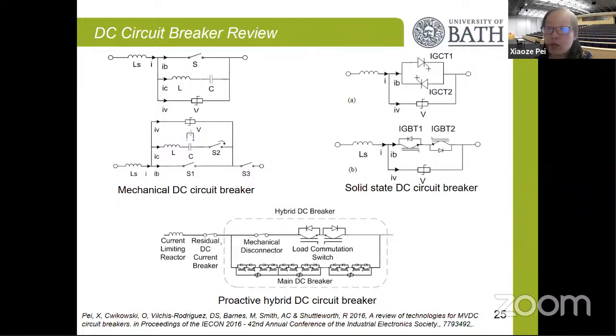However, one of the main problems is that the operation speed of the mechanical DC circuit breaker is quite limited. The commercial solution at the moment is about 30 to 50 milliseconds. This sounds fast, but for DC, the fault current may already increase to a higher level that the circuit breaker is not able to handle.